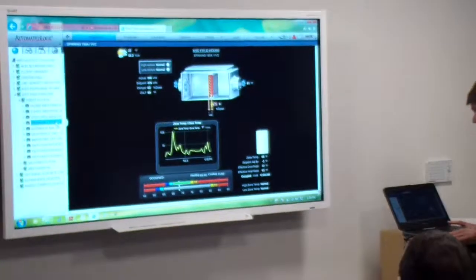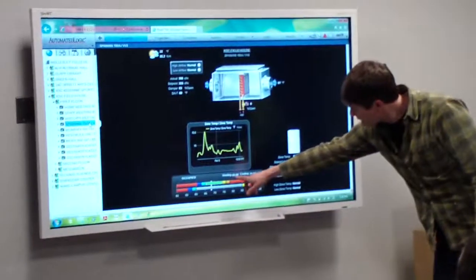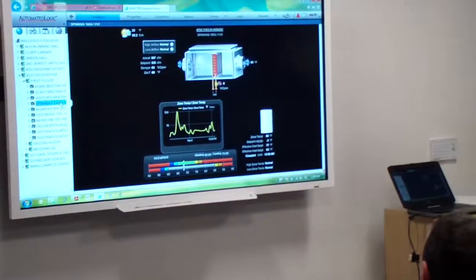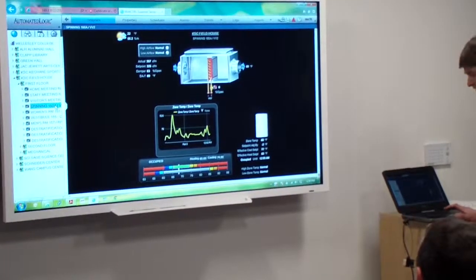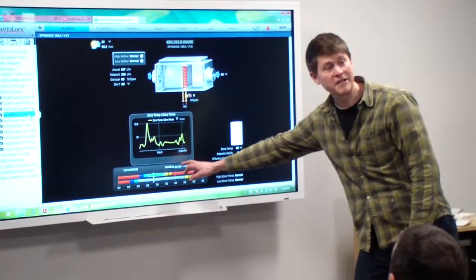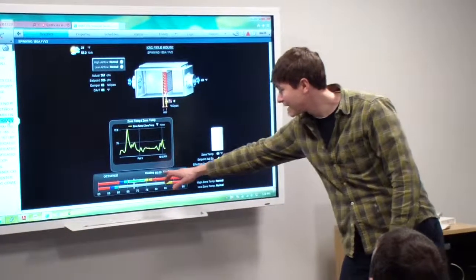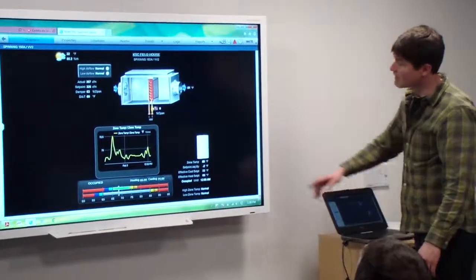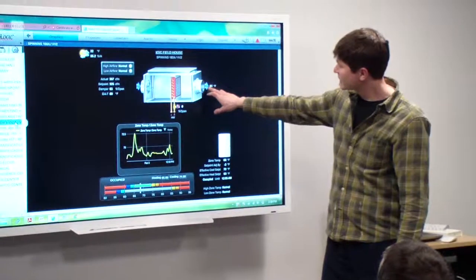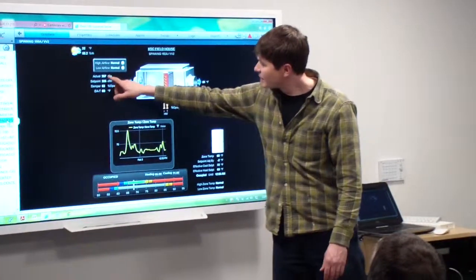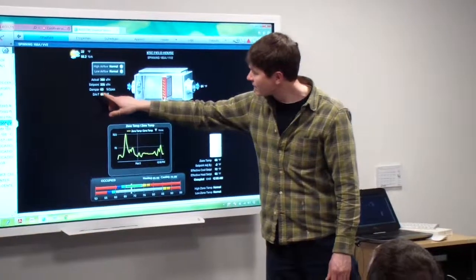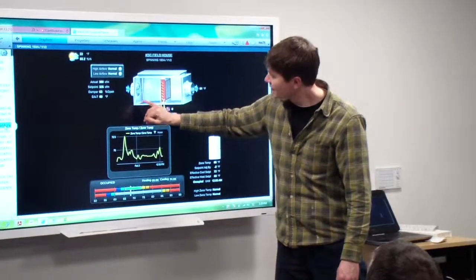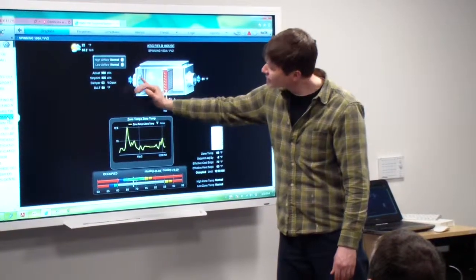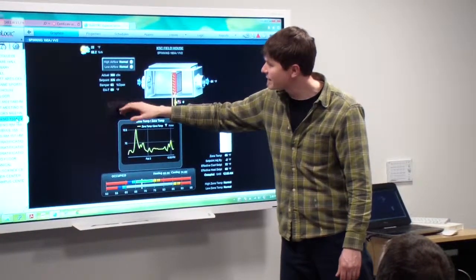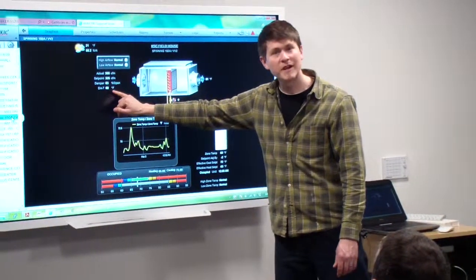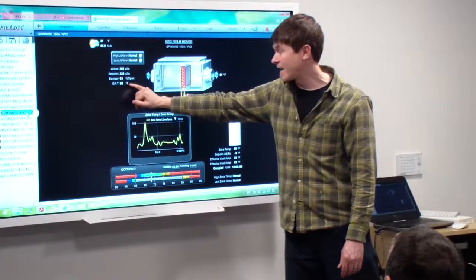Spinning room, you see your set points for the spinning room. Heating at 65, cooling around 74, which is all adjustable just by clicking on here and changing it to whatever the desired value is that you would like. You'll see your hot water valve percentage, what the unit's discharging. This is the amount of airflow that's coming out. The damper position, as you can see, the blade is almost fully open, so you've got 63% there. And then this discharge air temp value, that actually is what's coming out of the air handler at the moment.